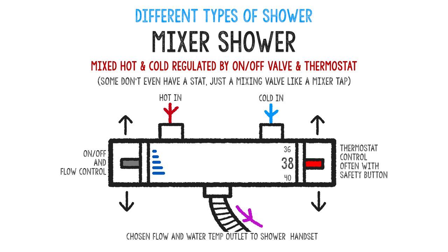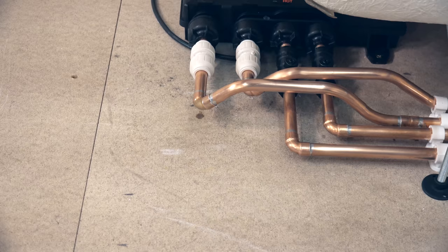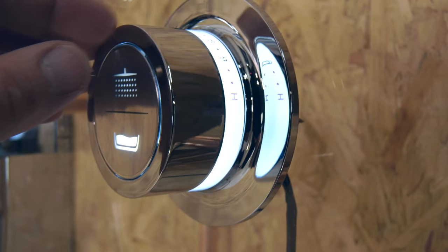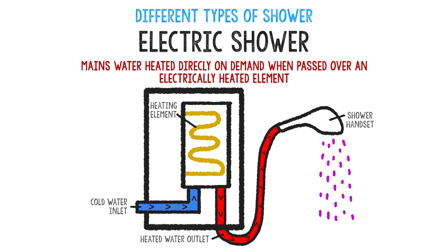These can have a standard handset or a pan overhead or both. Then we've got a digital mixer shower, a bit like the Mira Mode — you can have multiple outlets on this, so you can have a shower handset and overhead and even a bath fill. The hot and cold inlets go to a remote digital box where the water temperatures and flows are mixed according to a digital controller remotely installed inside the shower. I've already done a video on installing the Mira Mode, so pop back to our channel and check it out. Then we have the electric shower we're installing today: cold water mains passed over a heating element that heats up the water on demand. The big difference about the Mira Decor Dual is that not only do you have the shower handset, but you also have the overhead pan as well.